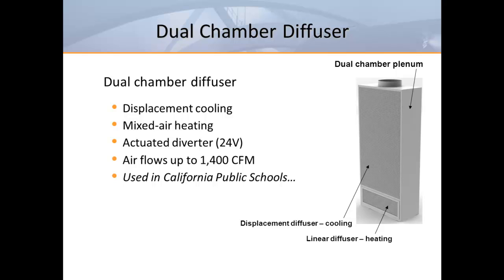The dual-chamber displacement diffuser was originally developed by Titus for a school district in Southern California — they wanted the advantages of displacement ventilation for their classrooms but didn't want a separate system for their mild heating requirements. This diffuser is built with a rear plenum that can supply air through either a large displacement panel for cooling or redirect the air through a lower grill section for heating. The reduced size of the lower grill increases the discharge velocity to get the horizontal projection needed for heating. The internal diverting damper can be activated by a small electric actuator, and a self-powered energy harvesting model is also being developed that will be completely standalone, requiring no power or external control signal.